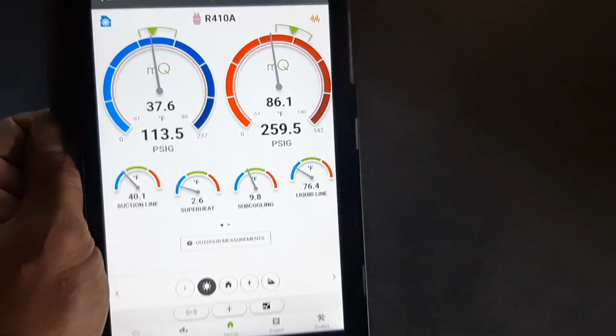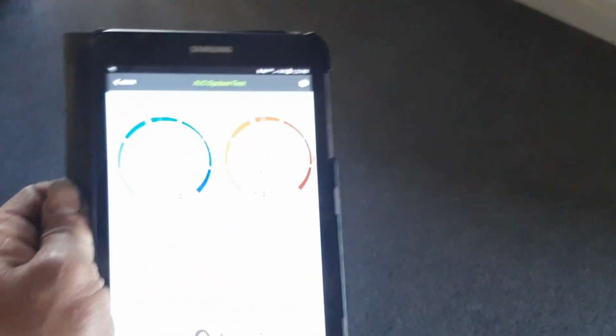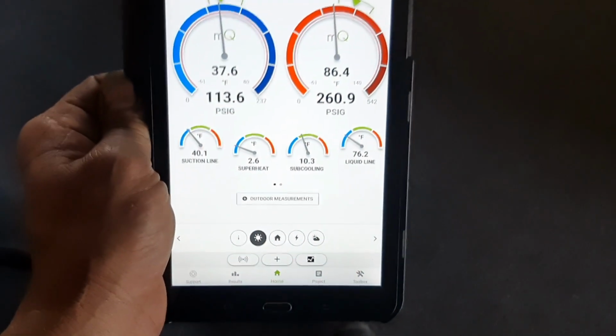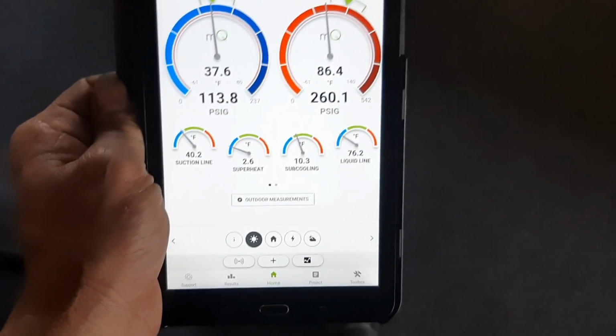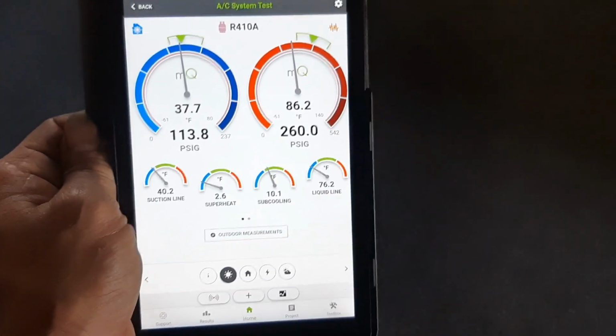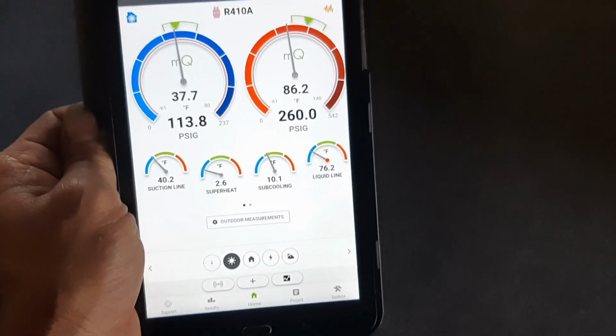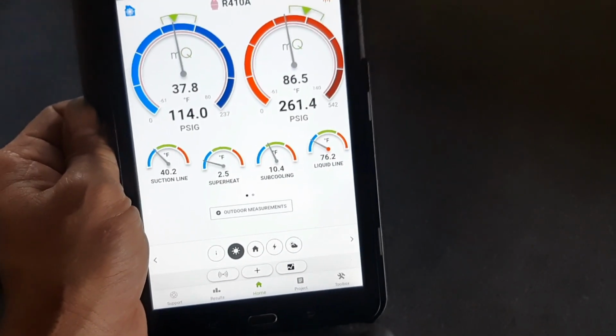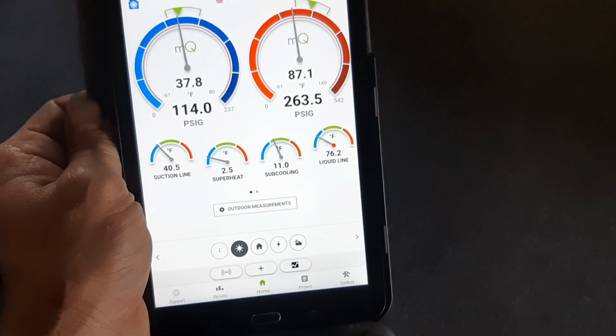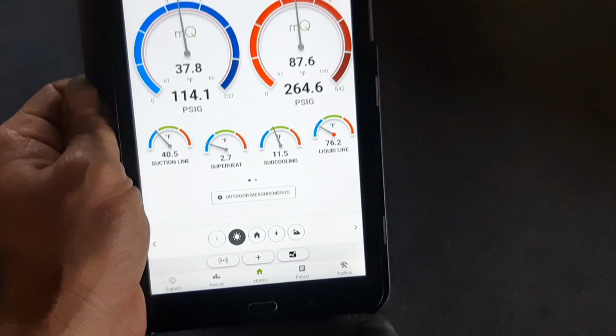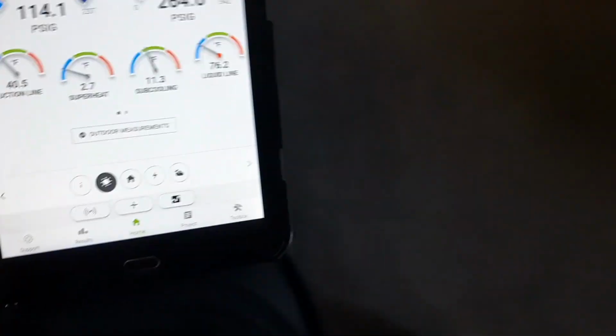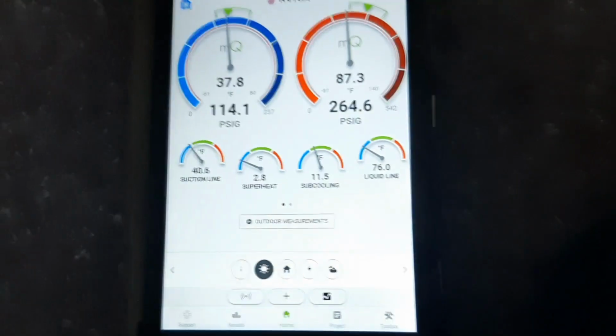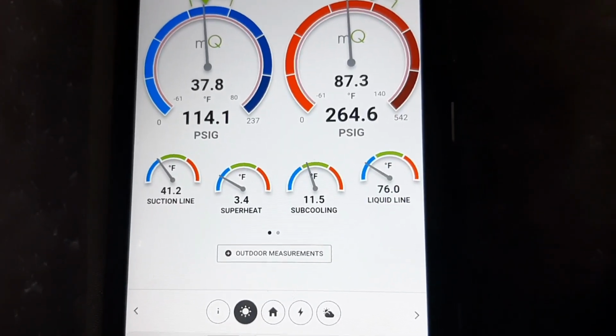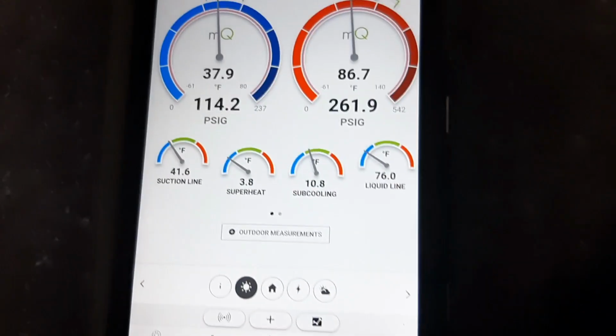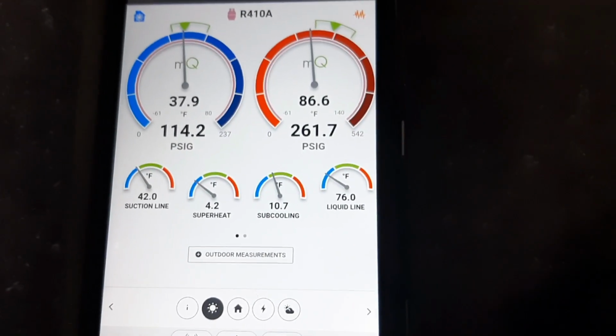But I mean, hell, it may have froze up. That may have been why they called, because they called and said this one wasn't running, and then he wanted all of them looked at. Of course, it was dirty at that point too, so now that it's clean, yeah, the superheat's going to improve now. That other damper must have just opened.